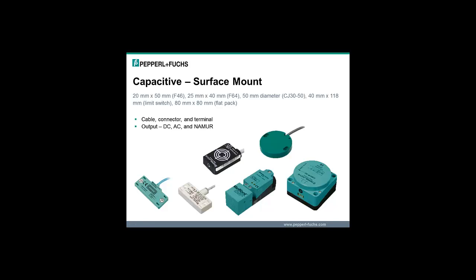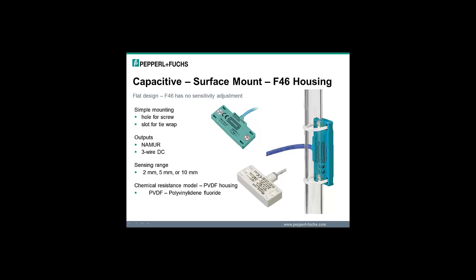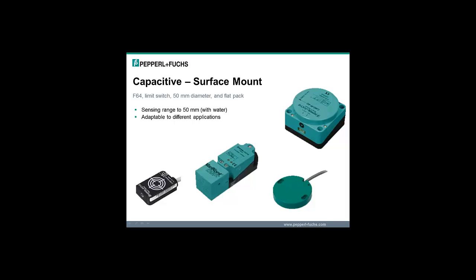The different housing types that are available are F46, which is 20 mm by 50 mm, F64, which is 25 mm by 40 mm, CJ30-50, which is a 50 mm diameter, standard limit switch size of 40 mm by 118 mm and standard flat pack size of 80 mm by 80 mm. With the F46 housing, you can mount using the screw hole or slots with a tie wrap. You can use the tie wrap if the F46 needs to be attached to a sight glass for level control. The F46 has no sensitivity adjustment but is available in 2 mm, 5 mm and 10 mm sensing ranges. There is also a PVDF housing that is more resistant to some chemicals. The F64, limit switch, 50 mm diameter and flat pack are very adaptable to solve different level applications.